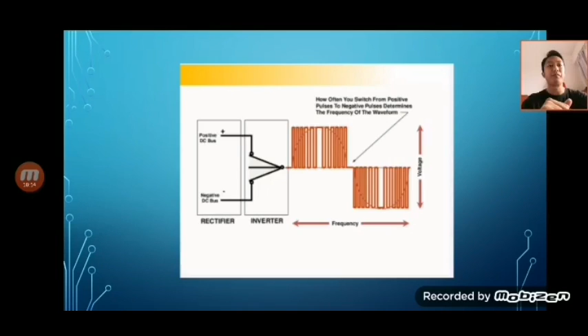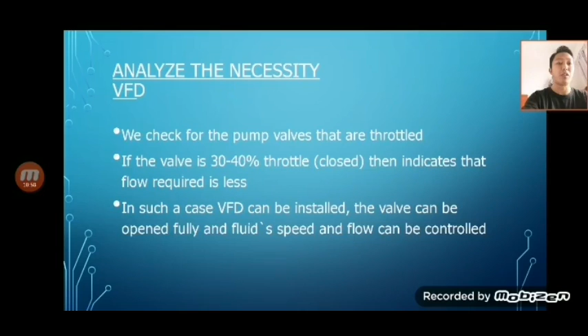So when is it necessary to use VFD in our activity? We can analyze the necessity of VFD. The first, we check for the valve that is throttled. If the valve is 30 until 40% throttle closed, then it indicates that the flow required is less. In such a case, VFD can be installed. The valve can be opened fully, and fluid speed and flow can be controlled by VFD. And this is the advantage of using VFD.